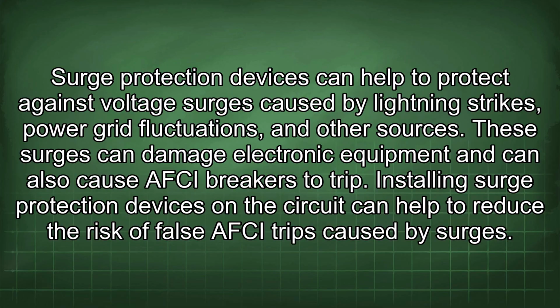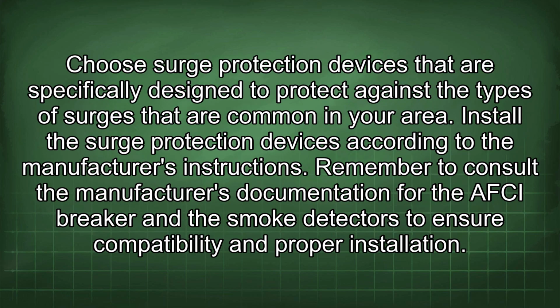Surge protection devices can help to protect against voltage surges caused by lightning strikes, power grid fluctuations, and other sources. These surges can damage electronic equipment and can also cause AFCI breakers to trip. Installing surge protection devices on the circuit can help to reduce the risk of false AFCI trips caused by surges. Choose surge protection devices that are specifically designed to protect against the types of surges that are common in your area. Install the surge protection devices according to the manufacturer's instructions.